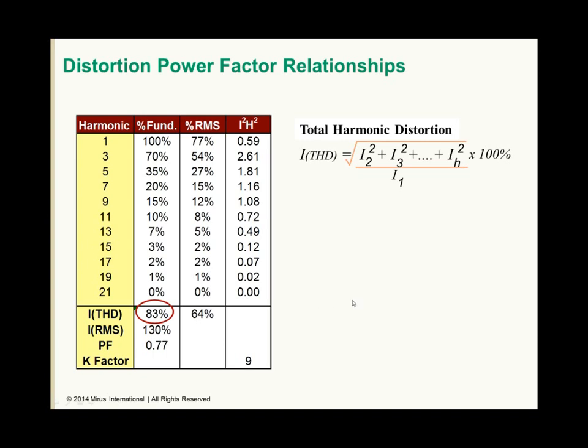We also have an I squared H squared component, and this is the factor that is used to determine our K rating, which is a measure of the extra heat generated by the load due to the harmonics, and it represents how a transformer can handle the nonlinear loads. So we have a K factor rating for this load profile, which is equal to 9, which is the sum of all the I squared H squared relationships.